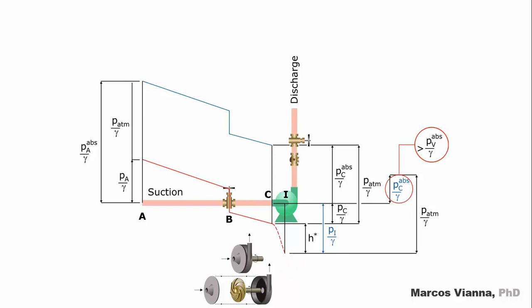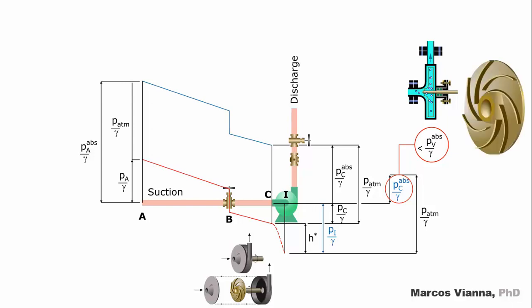When the water reaches the center of the impeller, the pressure must be greater than the vapor pressure of the water, or its state will be changed from liquid to vapor. If this happens, vapor cavities will form inside the pump. It will be suctioning liquid water no more, but a mixture of liquid and vapor. The efficiency of the pump decreases. And the impeller, designed to last years, will last only a few months because of the erosion caused by the cavitation phenomenon.